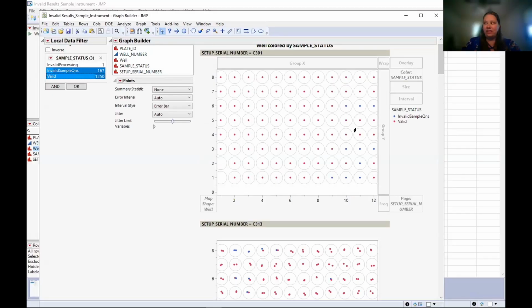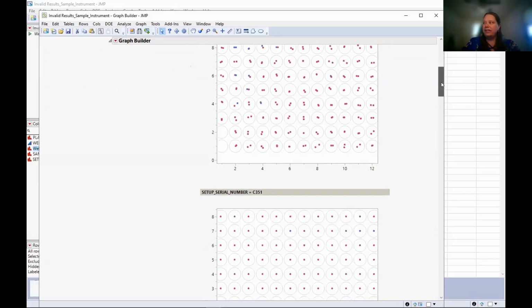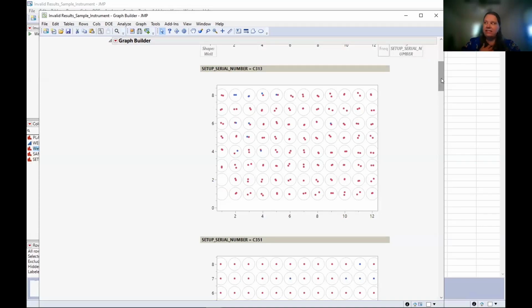but both of these scenarios show us two things about how the plate was seated. In this scenario, the plate was likely seated on our instrumentation so that the right side of the plate consumable was actually tipped, causing this specific error to occur. And on the second example, the pre and post maintenance, not really showing any change, but continuing to show that that plate placement was extremely important, where you're seeing those wells reproduce in the same type of area, even after a maintenance event.